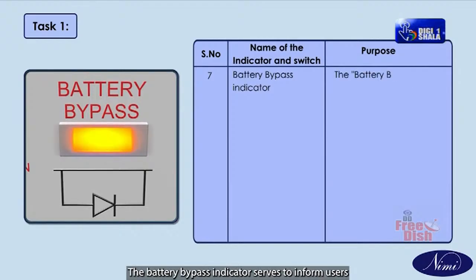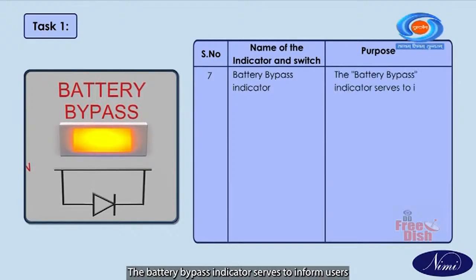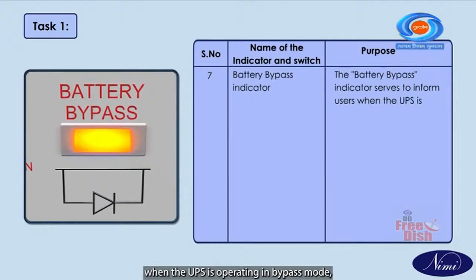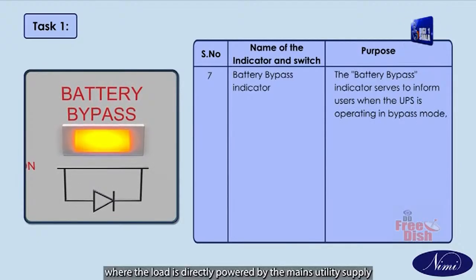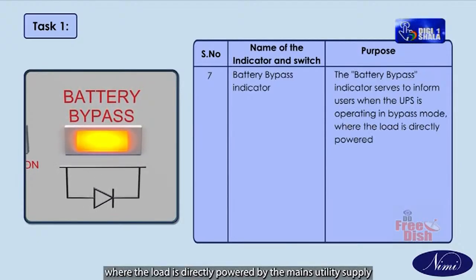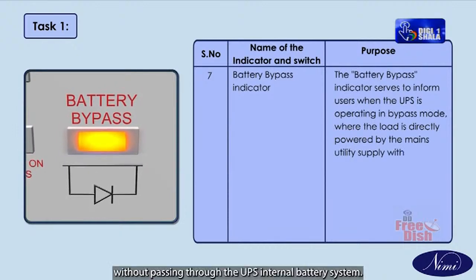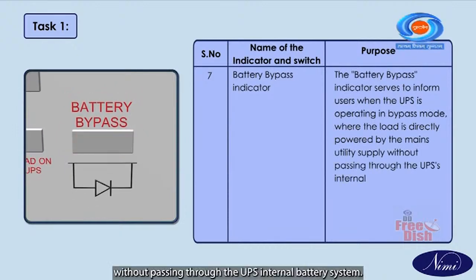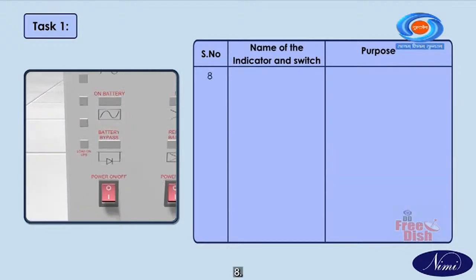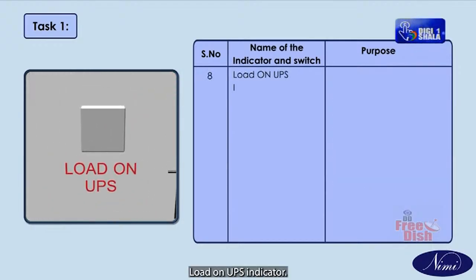The battery bypass indicator serves to inform users when the UPS is operating in bypass mode, where the load is directly powered by the mains utility supply without passing through the UPS internal battery system. Number 8. Load on UPS indicator.